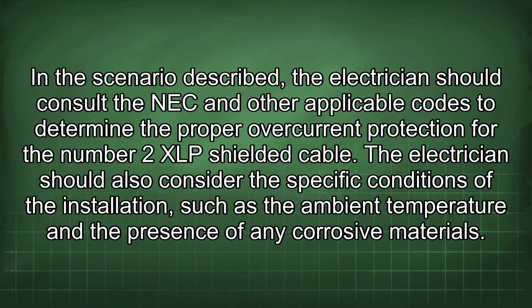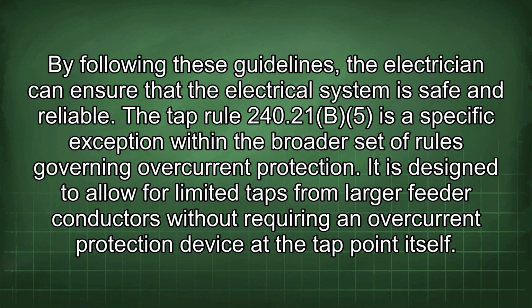In the scenario described, the electrician should consult the NEC and other applicable codes to determine the proper overcurrent protection for the number 2 XLP shielded cable. The electrician should also consider the specific conditions of the installation, such as the ambient temperature and the presence of any corrosive materials. By following these guidelines, the electrician can ensure that the electrical system is safe and reliable. The tap rule 240.21(B)(5) is a specific exception within the broader set of rules governing overcurrent protection. It is designed to allow for limited taps from larger feeder conductors without requiring an overcurrent protection device at the tap point itself.